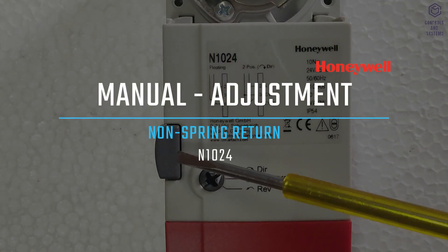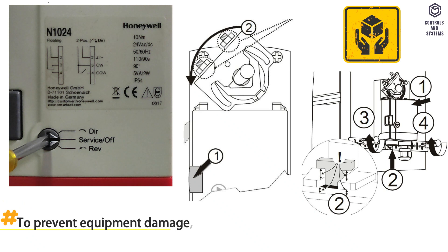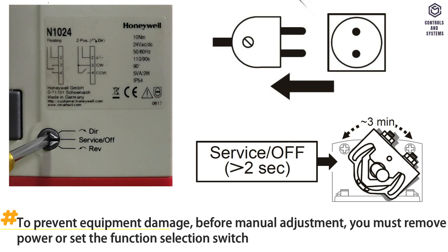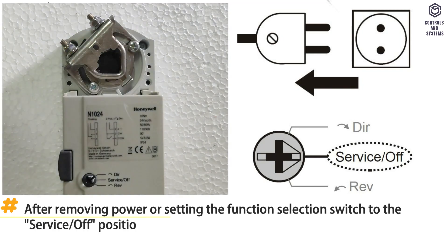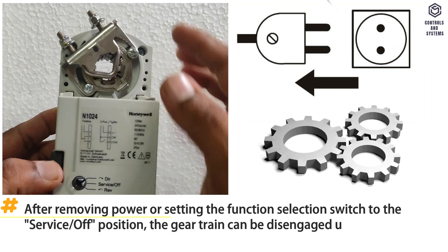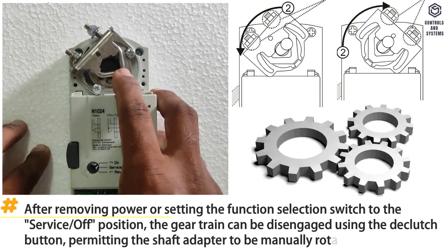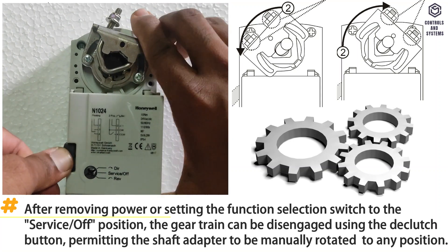Manual adjustment: To prevent equipment damage, before manual adjustment you must remove power or set the function selection switch to the service or off position. After doing so, the gear train can be disengaged using the declutch button, permitting the shaft adapter to be manually rotated to any position.